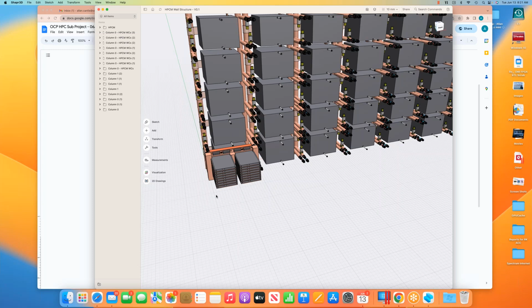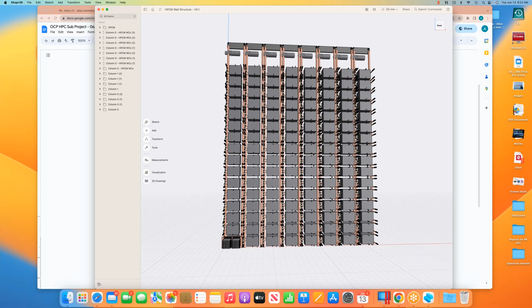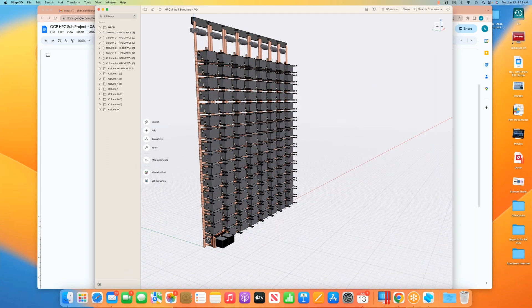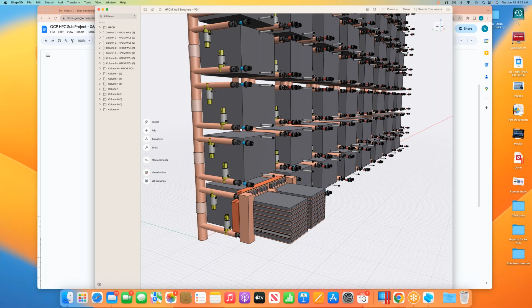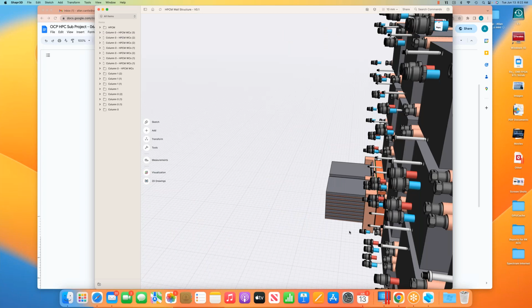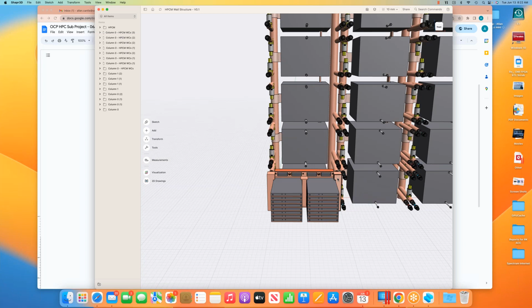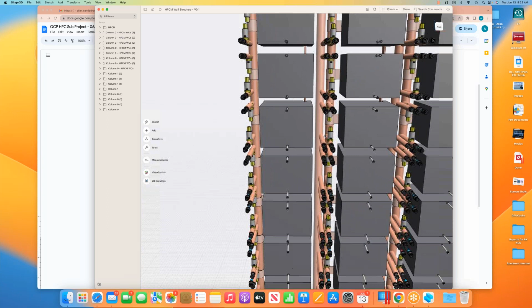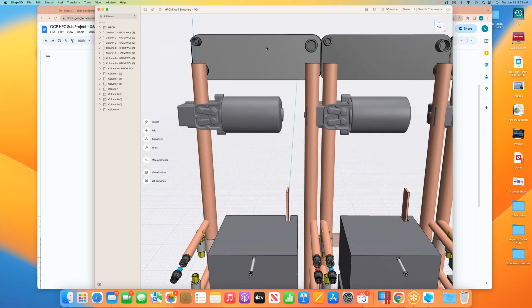The facility water will flow through the heat exchangers. Once you've exchanged the heat, the cold water will come down this column here, and in the non-thermosiphoning version it will be pumped down, with the pump somewhere in the loop. You'd have valves going into each of the modules. These valves, again this is just a cartoon so we need to turn it into something real, would control the flow of cold water into the module, such that the outflow of hot water on the hot side would be 65 degrees centigrade coming out of the module, and then all the hot water returns from all the modules would rise up and go back into the heat exchanger at the top.